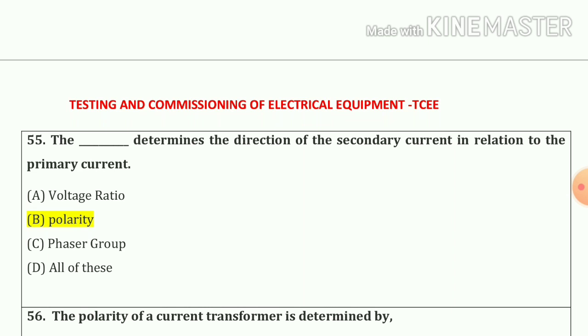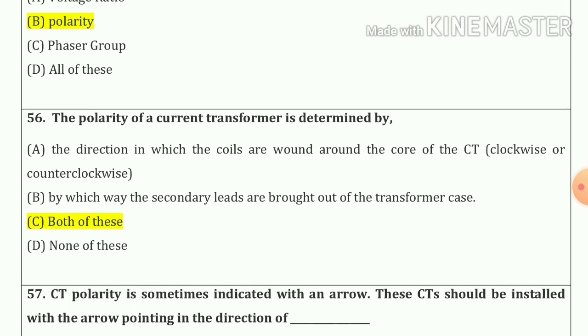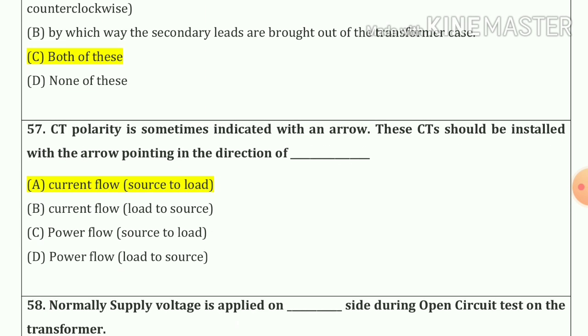Question number 55. The polarity determines the directions of secondary currents in relation to the primary current. So our answer is polarity, option number B. Now question number 56. The polarity of current transformer is determined by, so it is determined by option number A and option number B also. So our answer is option number C, both of these. Now question number 57. CT polarity is sometimes indicated with an arrow. These CTs should be installed with the arrow pointing in the directions of current flow, source to load.